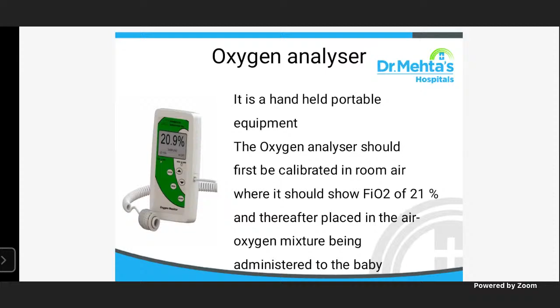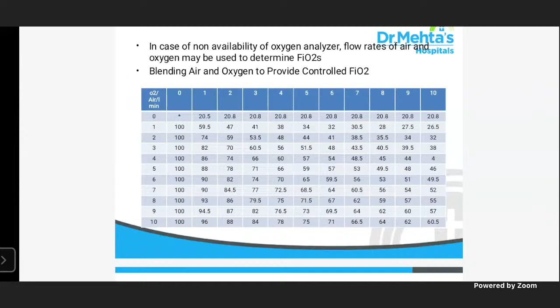In case of non-availability, if you don't have an oxygen analyzer, this is the flow chart to titrate the oxygen or to set the oxygen rate. So flow rate and the oxygen rate. If you are keeping 1 liter of oxygen and 1 liter of flow rate, for example, the baby will get 59.5% of FiO2. So this is a simple calculation we can fix in the level 3 or the baby care area. If you don't have any oxygen analyzer, we can use this chart and keep the oxygen saturation level at the target level. That is about the oxygen analyzer.